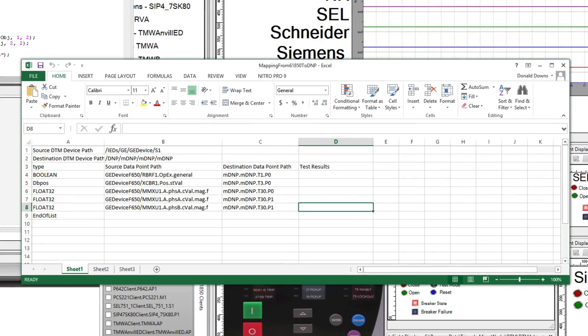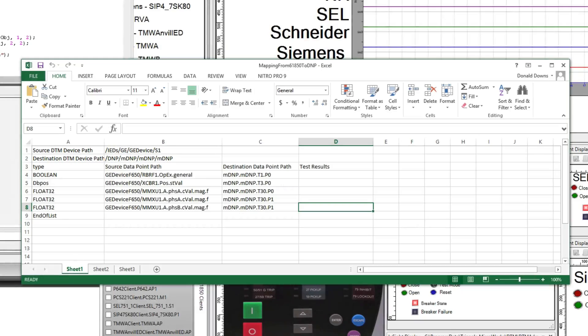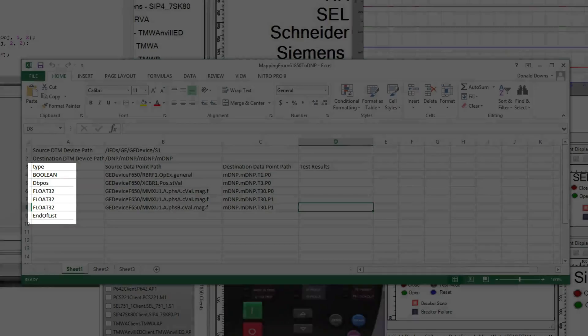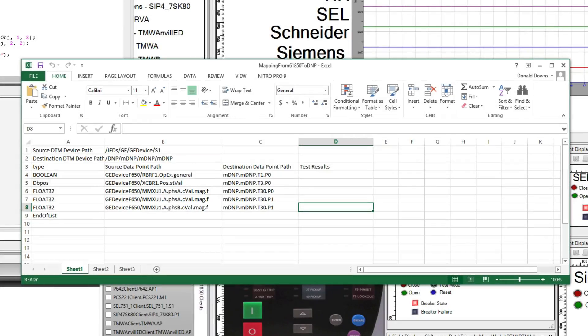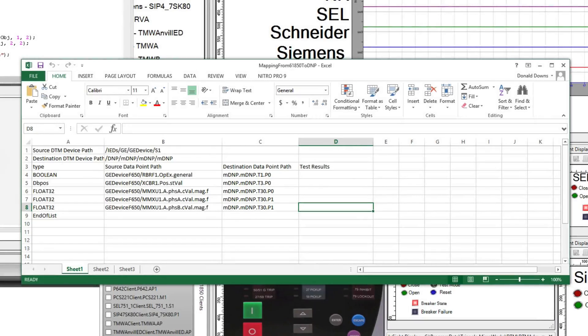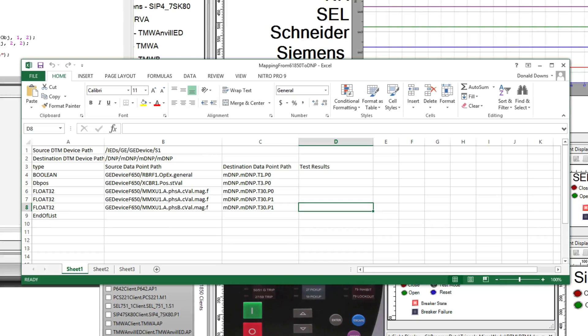The Excel spreadsheet contains the following information: source and destination device paths, data type, source data point path, and destination data point path. The end of list designation marks the end of the mappings. This technique allows an unlimited number of mappings to be tested.